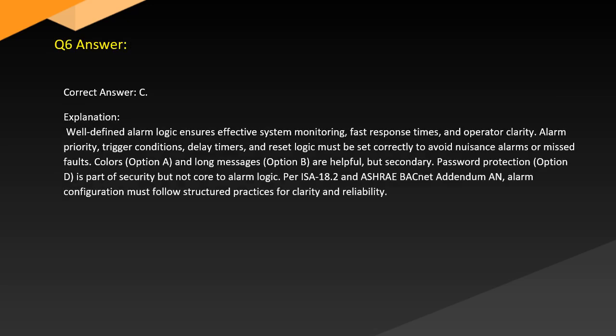Answer. Correct answer: C. Explanation. Well-defined alarm logic ensures effective system monitoring, fast response times, and operator clarity. Alarm priority, trigger conditions, delay timers, and reset logic must be set correctly to avoid nuisance alarms or missed faults. Colors, option A, and long messages, option B, are helpful but secondary. Password protection, option D, is part of security but not core to alarm logic.